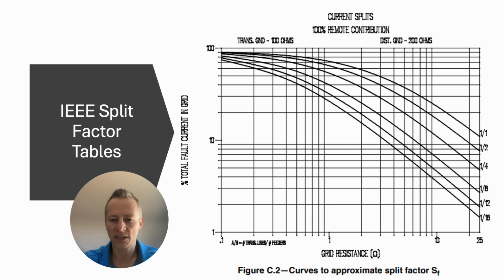This is one of many tables. They have a table for 100 ohm transmission grounds and 200 ohm distribution grounds, but they also have tables for 25 ohm distribution grounds and a number of tables that have different arrangements of this data. Generally you pick. The slash here means one transmission line and one distribution line connected to your station. So if you know your grid resistance and your one transmission line, one distribution line, you can read off over here on the left the percentage of split factor. You read that off the chart to get your percentage split factor to tell you how much current goes into the grid versus what is returned by other means, right?